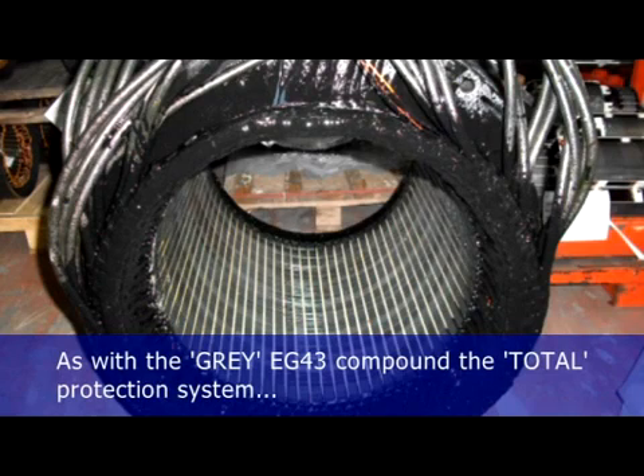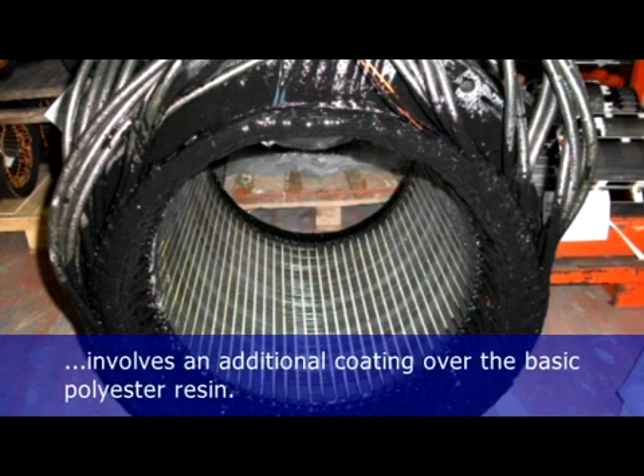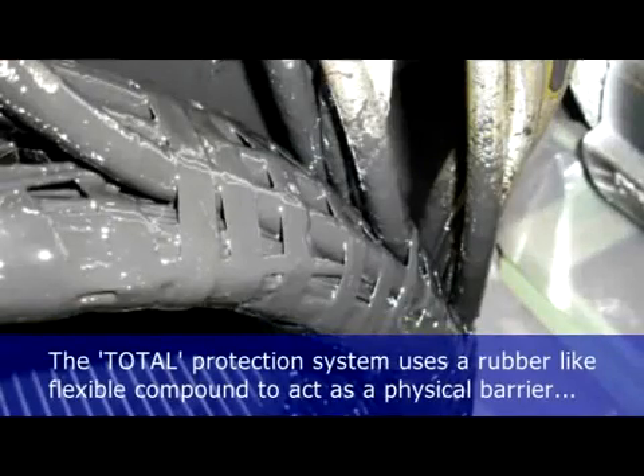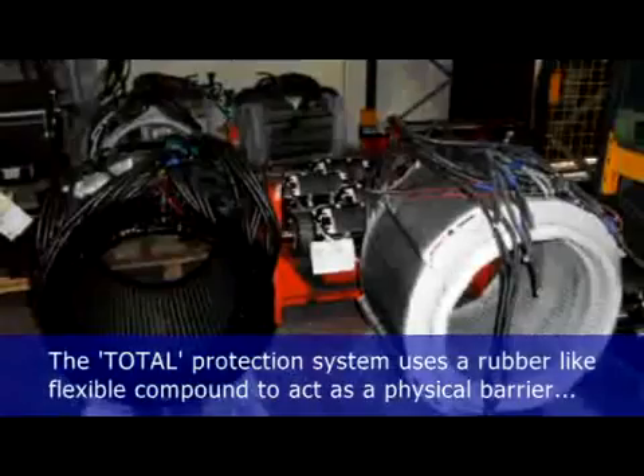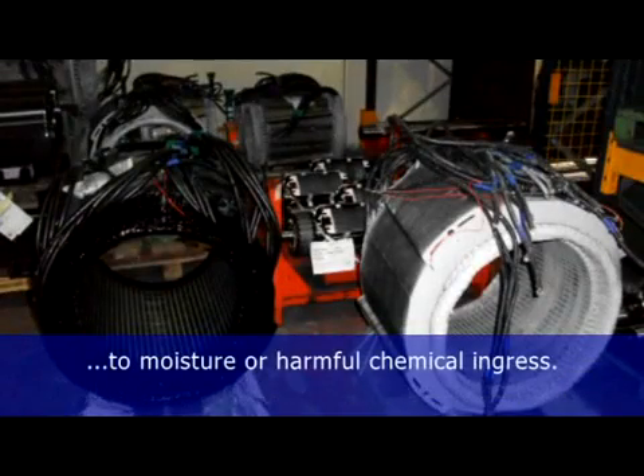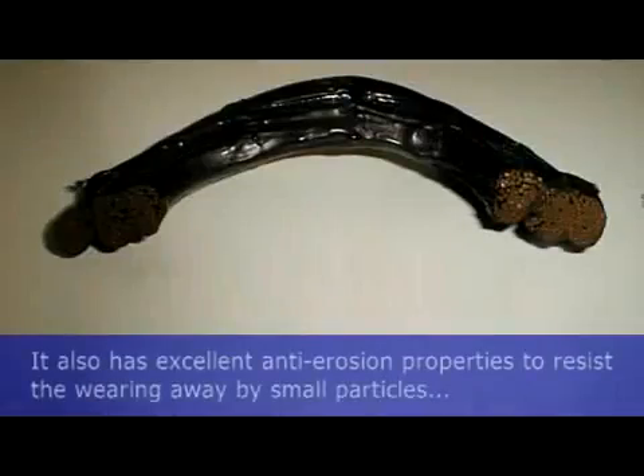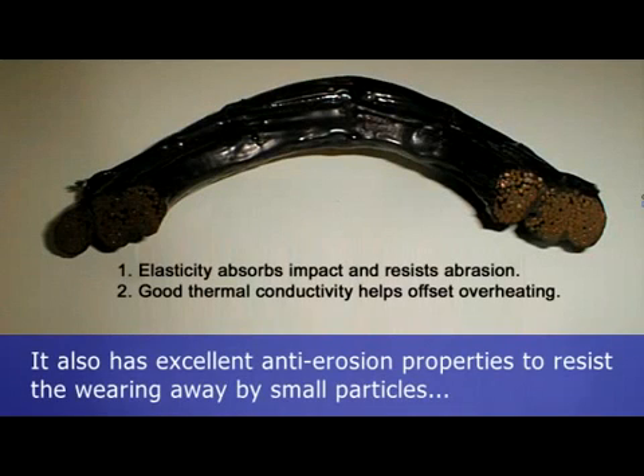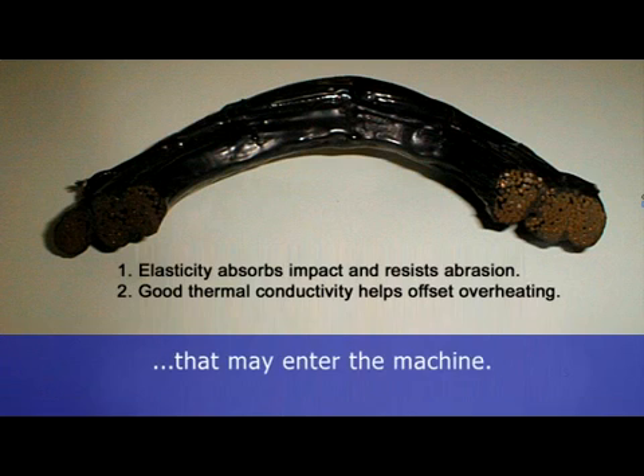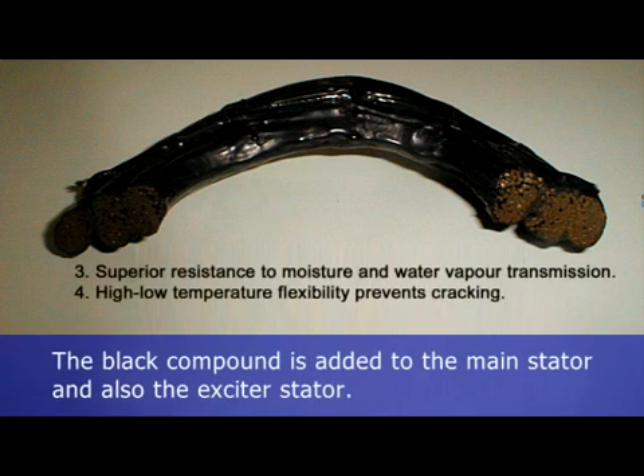As with the grey EG43 compound, the total protection involves an additional coating over the basic polyester resin. The total protection system uses a rubber-like flexible compound to act as a physical barrier to moisture or harmful chemical ingress. It also has excellent anti-erosion properties to resist the wearing away by small particles that may enter the machine. The black compound is added to the main stator and also to the exciter stator.